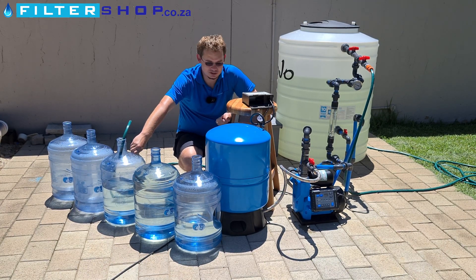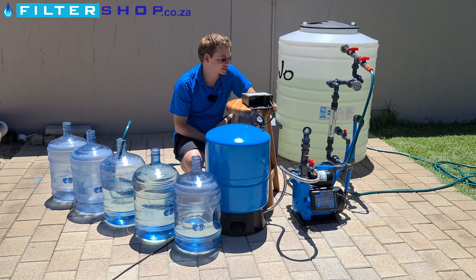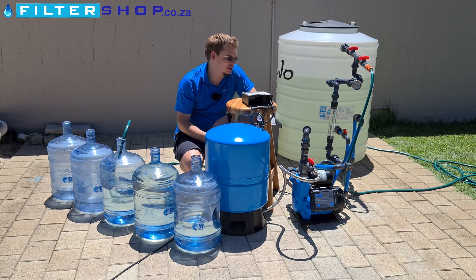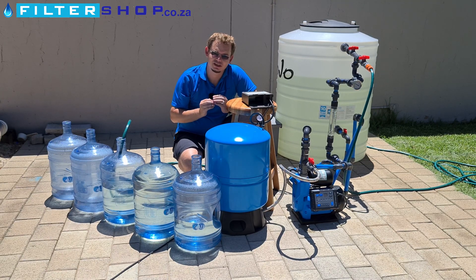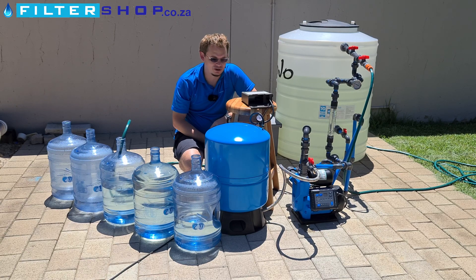Things to take away from this: make sure when setting up a system like this that you match your pump and pressure tank's pressure settings to get the maximum usage out of the tank. You'll also get the most benefit with a pump controller where you can actually set the on and off points, because then you have more leeway to set where it turns on and off. We'll definitely test it with a normal dumb pump controller as well just out of interest to see what we actually get.